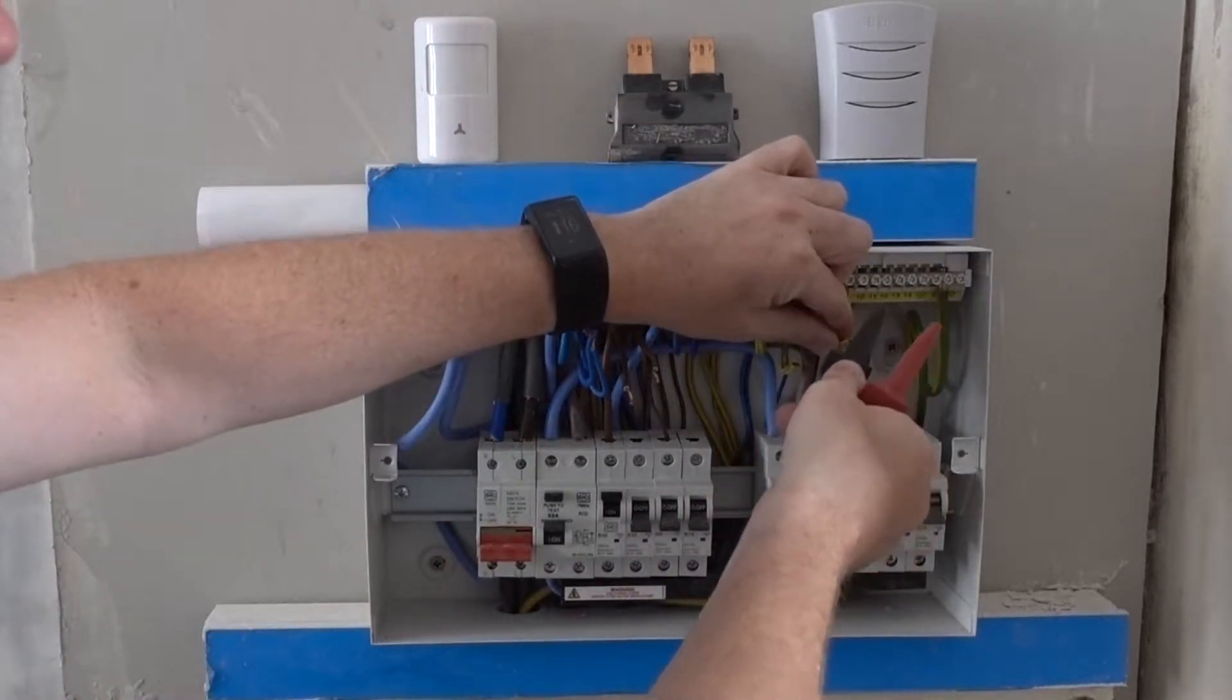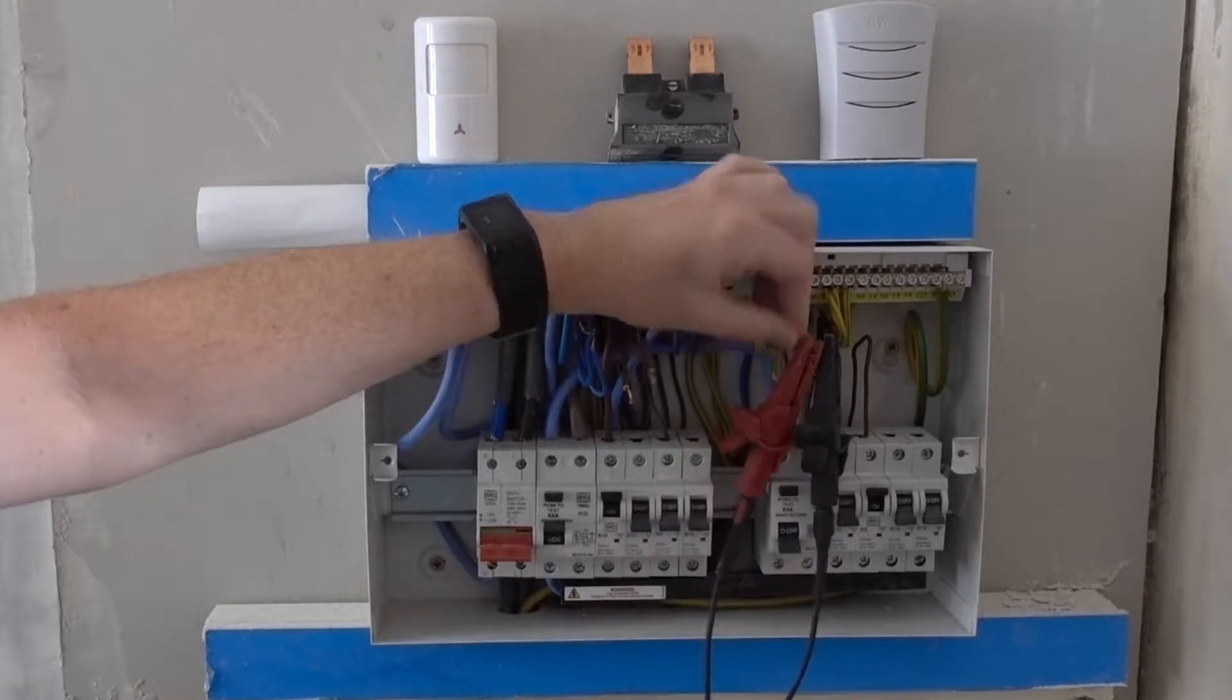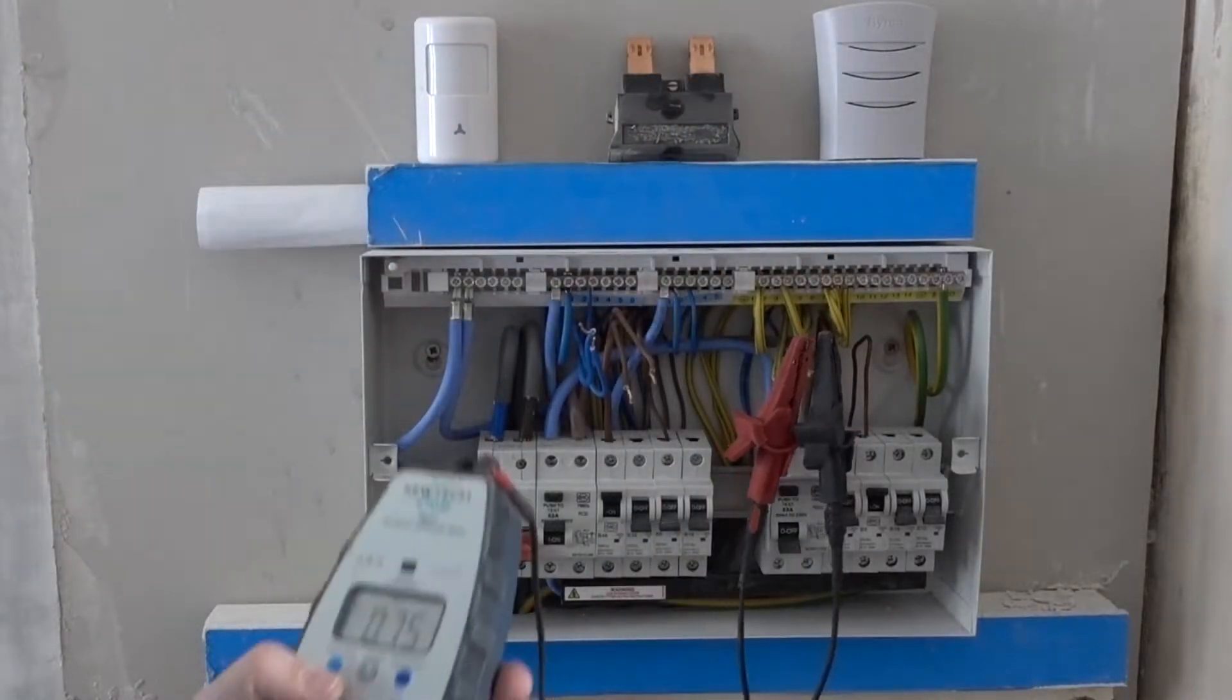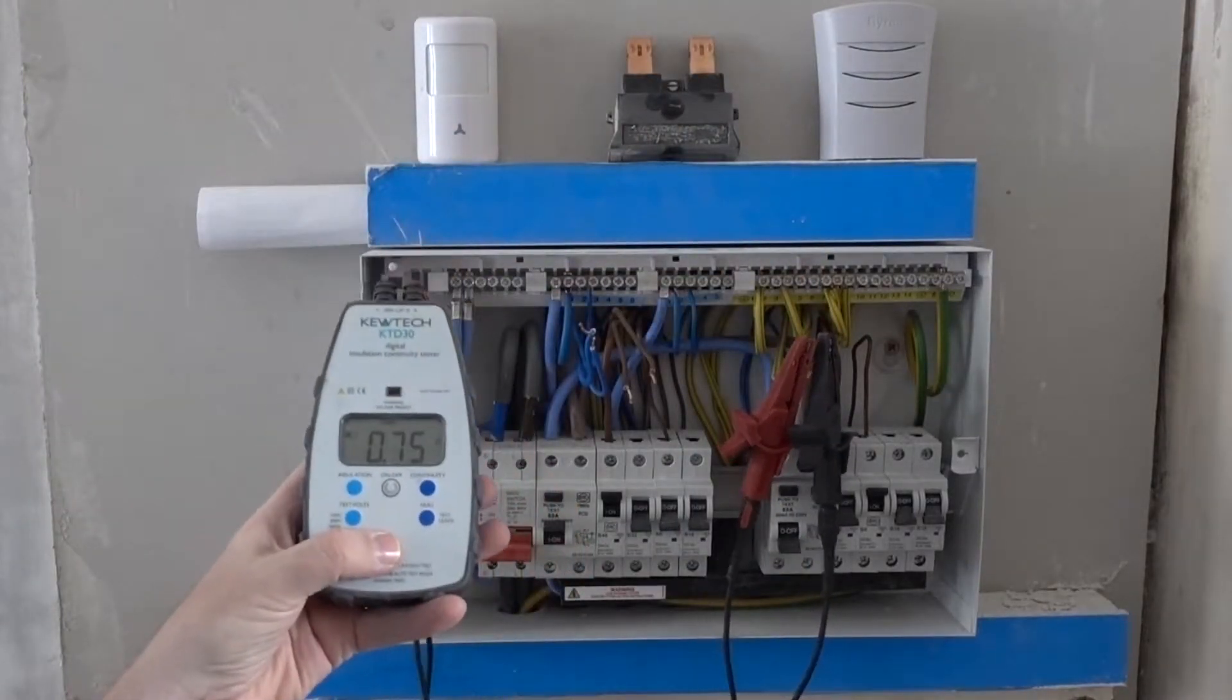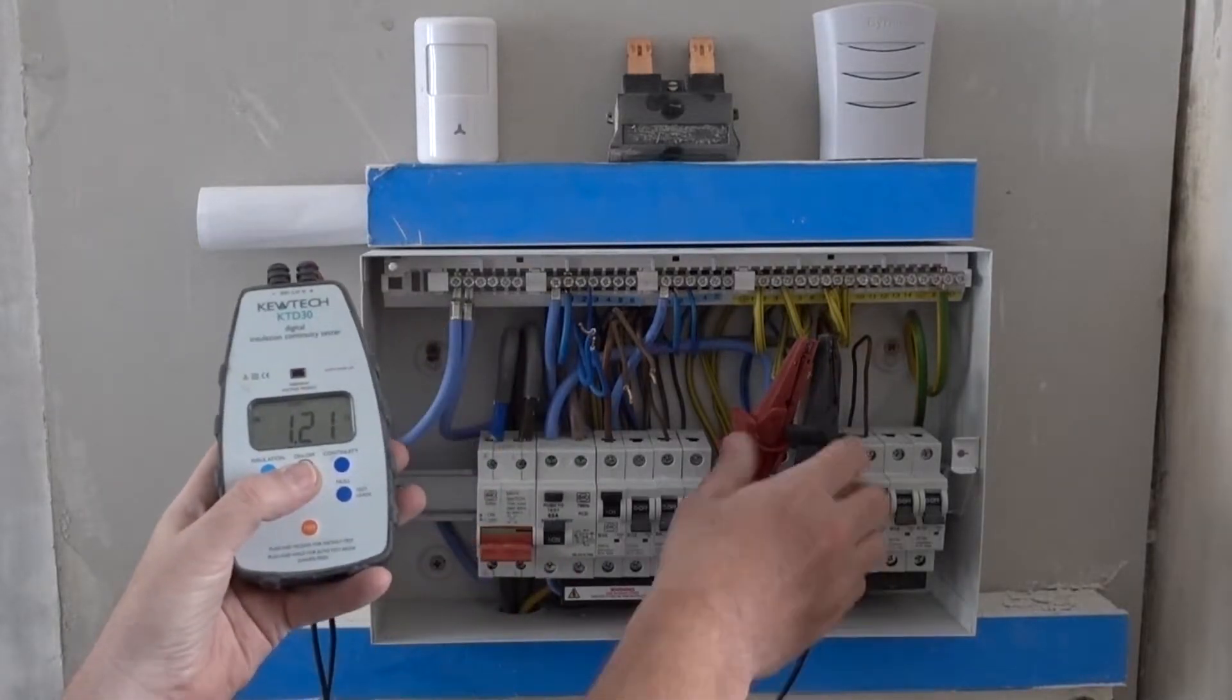And then let's just test continuity on the earth, the protective circuit. This is obviously a smaller wire. So we're expecting just a bit under double. So yeah, 1.21. That's exactly what we'd expect.